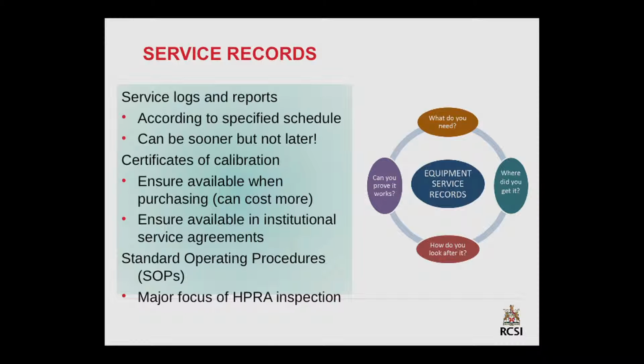You might be using equipment belonging to another department. For example, a freezer in the laboratory: you need to be able to link the serial number on that freezer to your tracking log, and you need to know that you have access to their service records and to the temperature records, and that you're going to be able to put copies of the temperature records in your site files. And sometimes the sponsor may provide study-specific equipment, and in that case they'll specify what the care of it should be, and will look after its maintenance to a large extent. But if at the end of the trial they decide that they're not taking that back and they're going to donate it to you for future use, then you need to add that into your equipment lists.